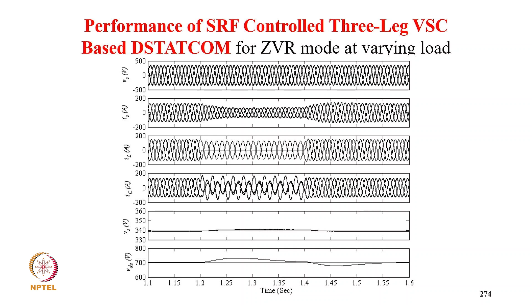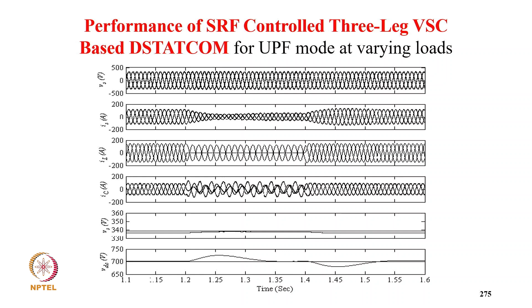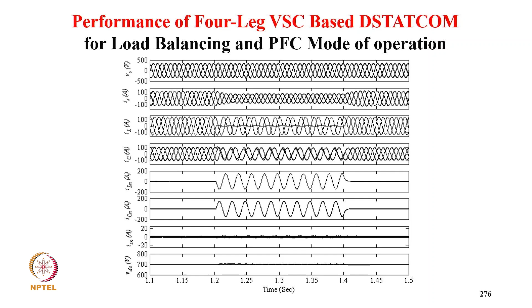This is the performance at unity power factor at varying load. You can see that with unbalanced load, load compensation is provided here. You can see the DC link voltage. Similarly for load balancing and power factor mode, load balancing is shown as well as power factor, and neutral current compensation is provided because it is a three-phase four-wire system. The inverter feeds exactly the opposite of the load current, so that the supply neutral current is made zero.